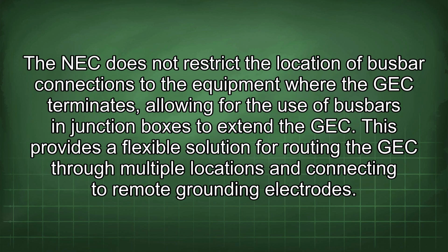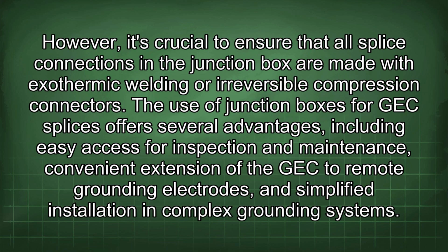The NEC does not restrict the location of busbar connections to the equipment where the GEC terminates, allowing for the use of busbars in junction boxes to extend the GEC. This provides a flexible solution for routing the GEC through multiple locations and connecting to remote grounding electrodes.